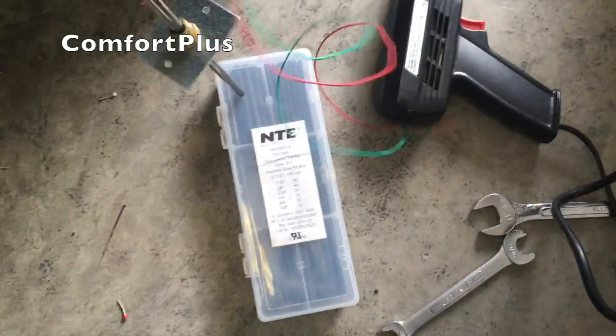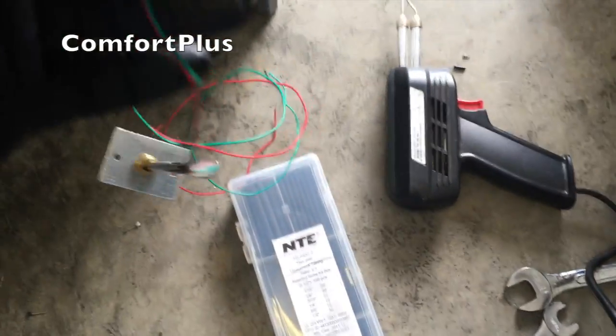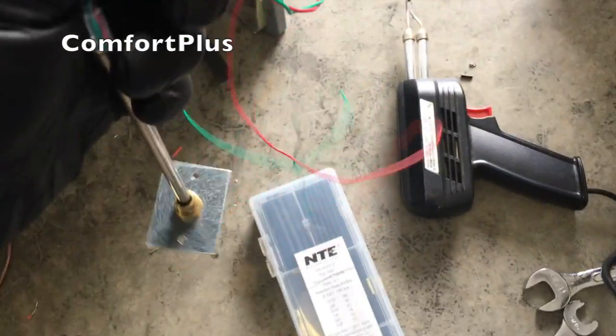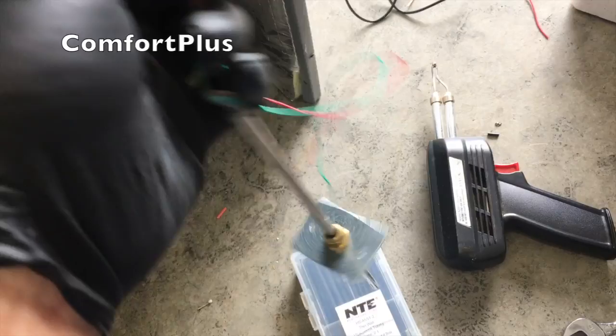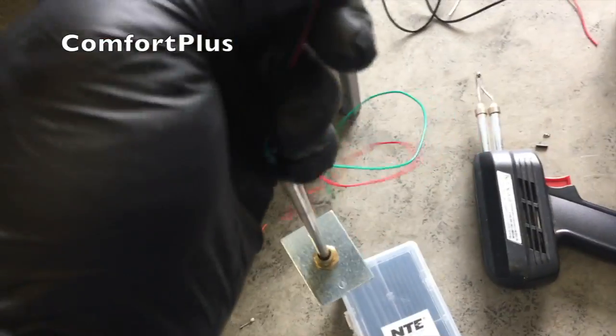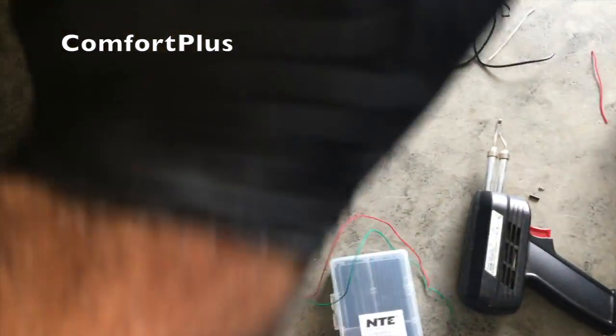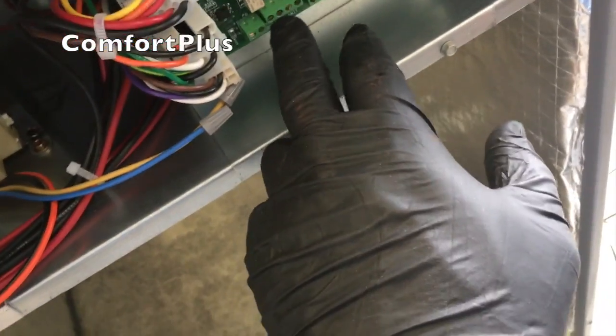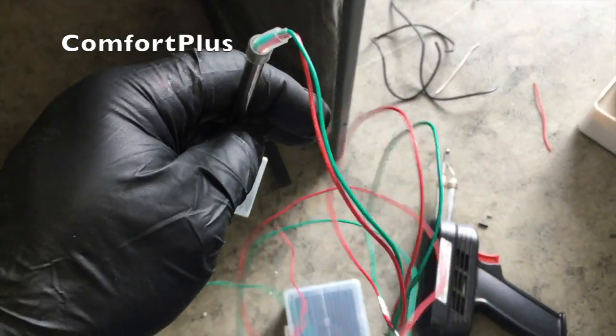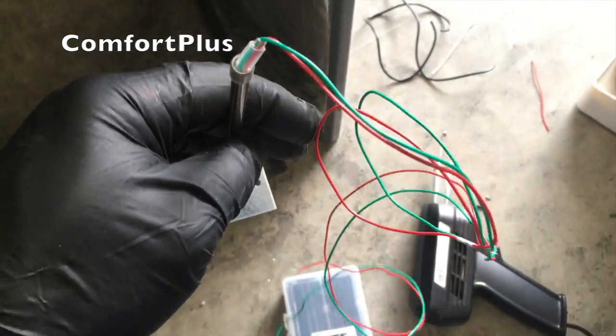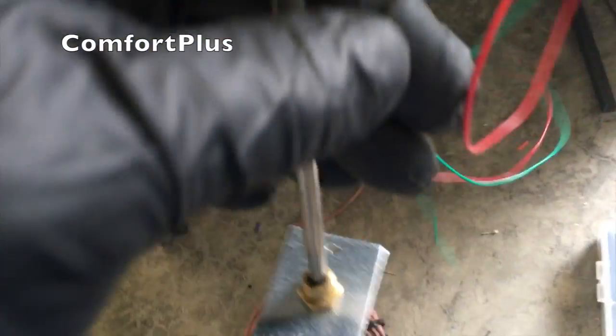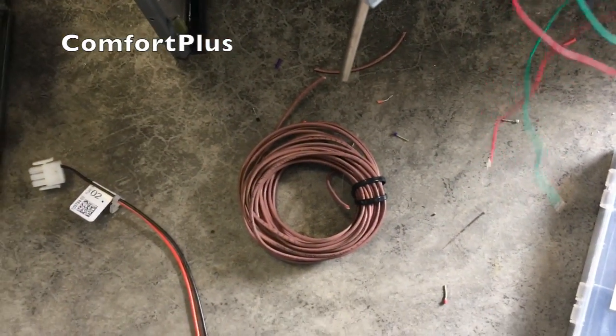So while I've got my heat shrink stuff out, I'm going to go ahead and put a 2-conductor thermostat wire on it down here close, past that break, and I will run that all the way to the zone panel in a separate cable. Since it's actually carrying resistance, and all the other stuff is carrying voltage or just a make or break connection, with the exception of the bus, which will be a separate 4-conductor cable anyway. So I'll go ahead and put the 2-conductor wire on this, and I'll be ready to drag it up to the zone panel when I get ready.